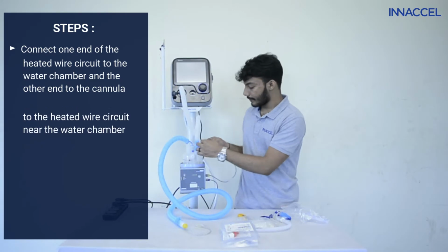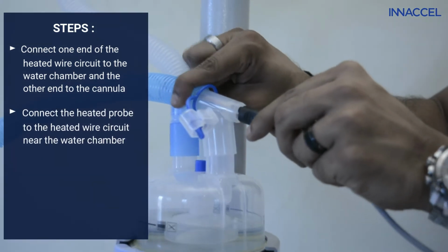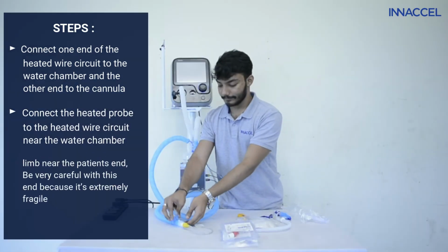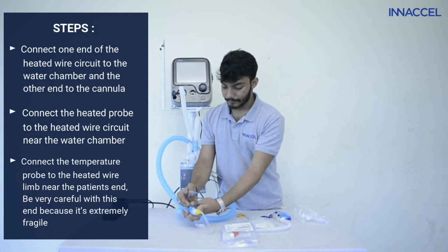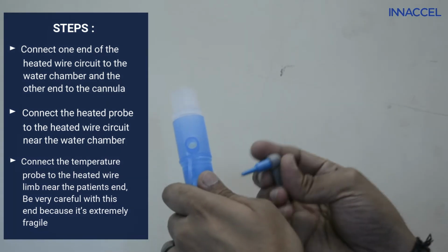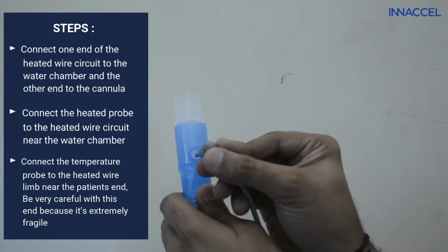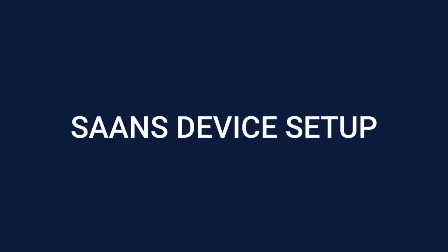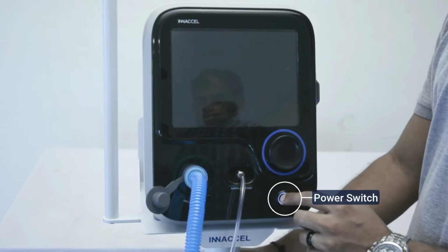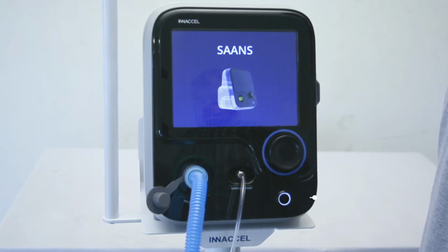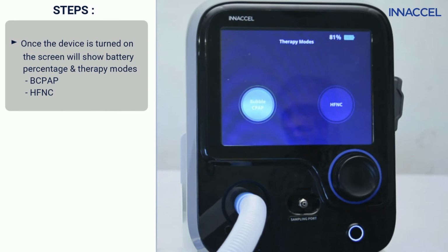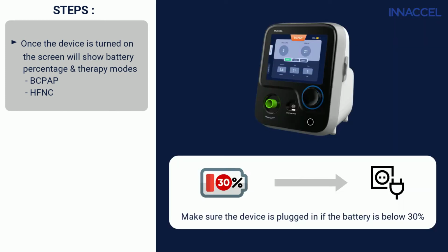Connect the heated probe to the heated wire circuit near the water chamber. Connect the temperature probe to the heated wire limb near the patient's end. Be very careful with this end because it's extremely fragile. SAANS device setup. Switch on the device by gently pushing the power button. Once the device is switched on, you will see the battery and available mode. Make sure the device is plugged in if the battery is below 30%.